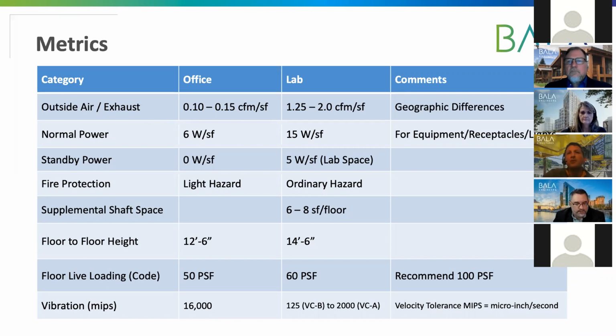And then for the vibration requirements, this gives you an idea of the difference between an office requirement and the bare minimum lab qualification. It's almost off by a factor of 8. So typically it's pretty expensive to upgrade the entire floor of the lab to qualify for this requirement. So what we've seen is, depending on the piece of equipment or the certain lab activities that are more localized within the building, we'll just reinforce those specific areas.